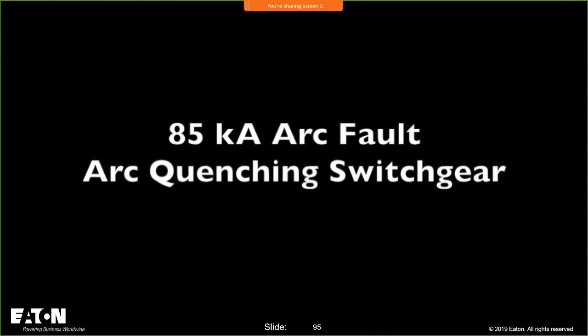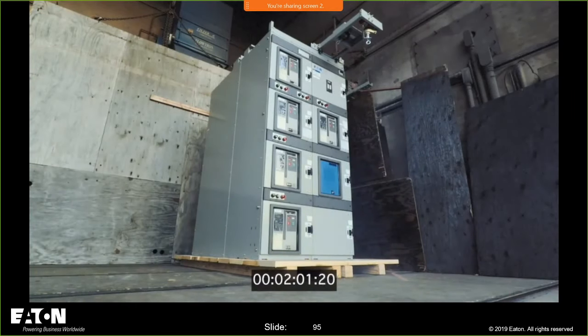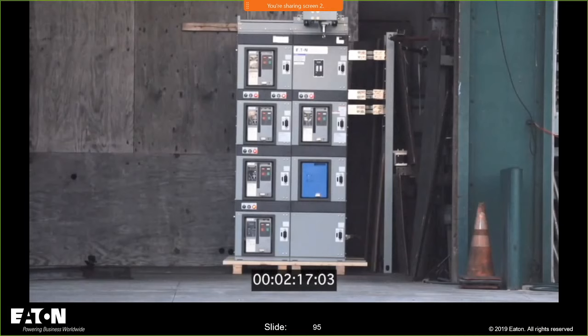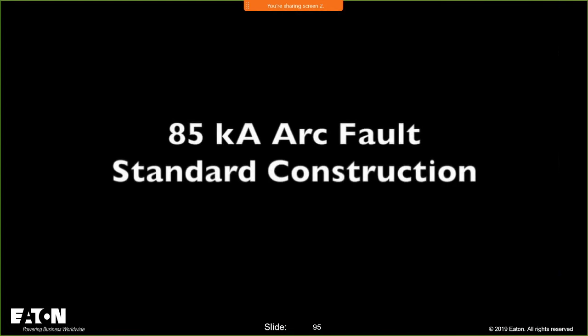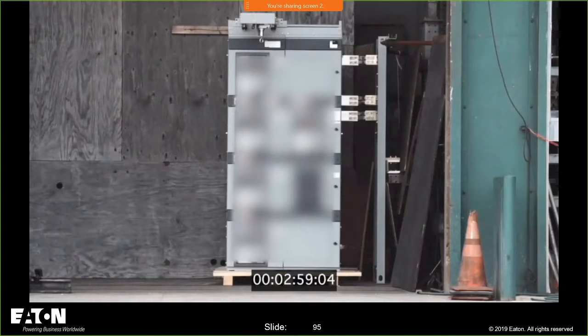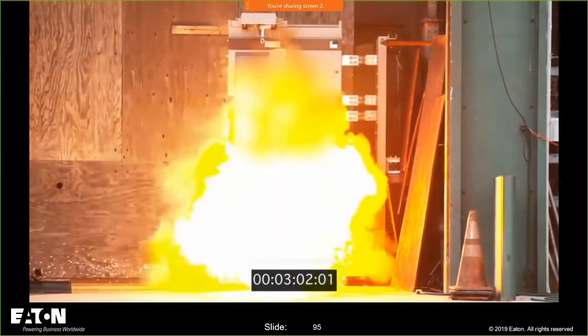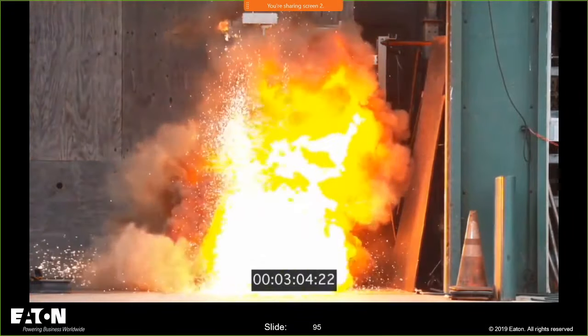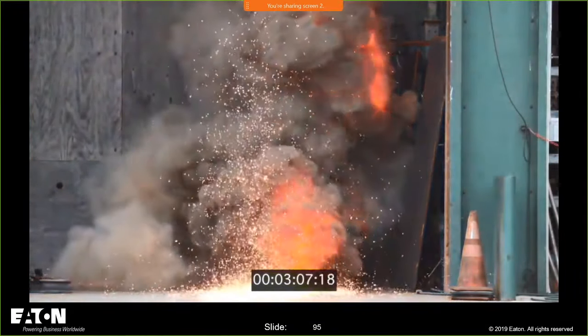Now we're going to do the exact same test with an arc quenching. That's the exact same test. It operates faster than around 0.004 seconds. You can be in front of that gear and have that go off. You can have the doors open. You might have to change your shorts afterwards, but you're not going to go home injured if you have the technology in place to take that type of fault by simply putting a blue box in there and a relay together, working in connection with each other.